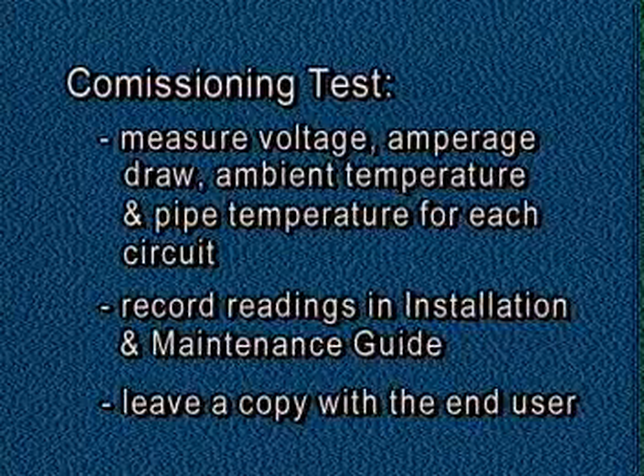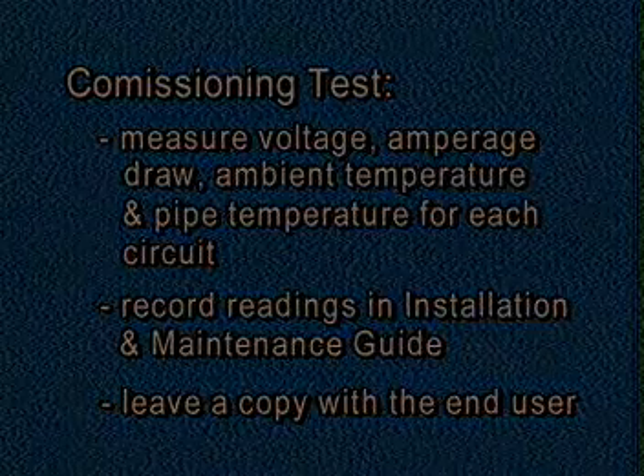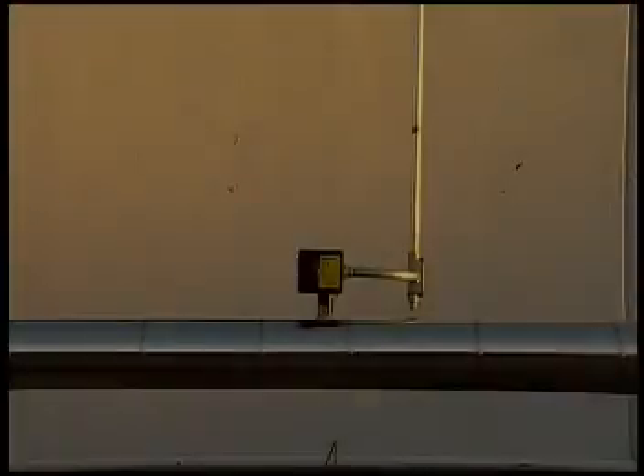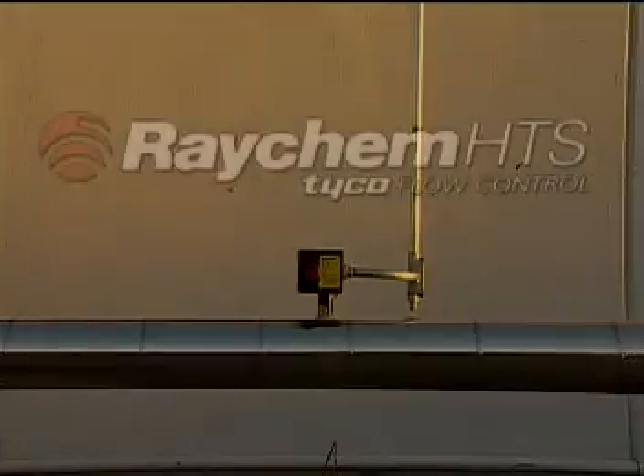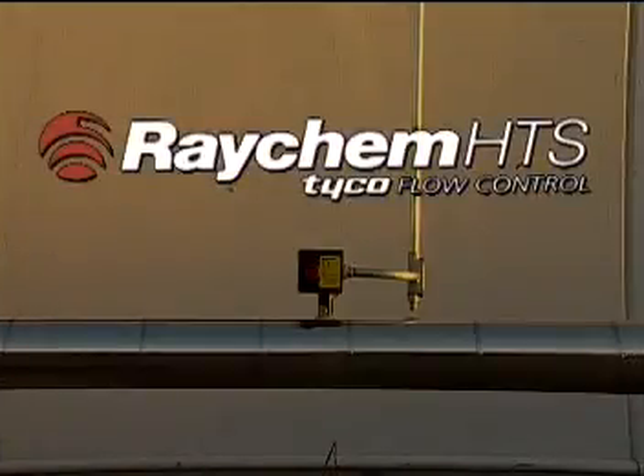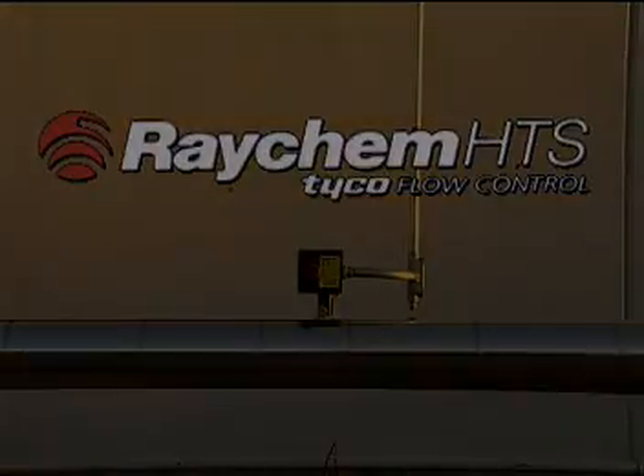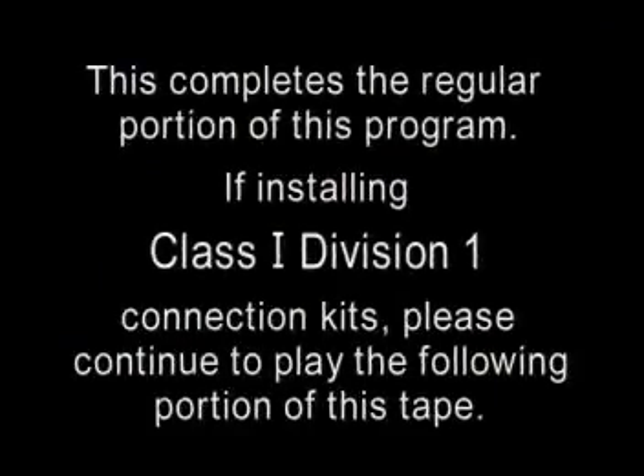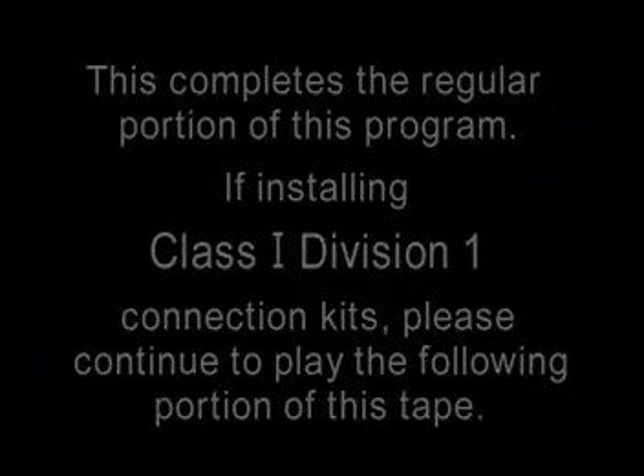This completes the installation of the self-regulating heating cable, and the system should now operate at peak performance regardless of the weather. If you have any further questions, contact your local Raychem representative. This completes the regular portion of this program. If installing Class 1 Division 1 connection kits, please continue to play the following portion of this tape.